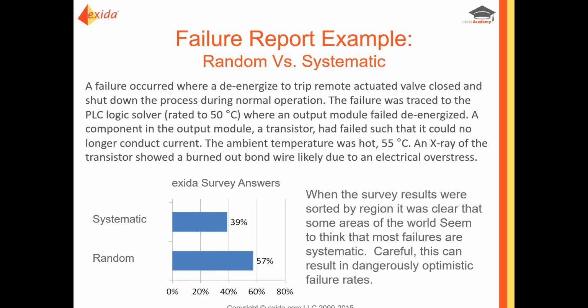So you need to be extremely careful about throwing away systematic failures. The bottom line is any data collection system that's of a high quality records all events without attempting to classify them random versus systematic.